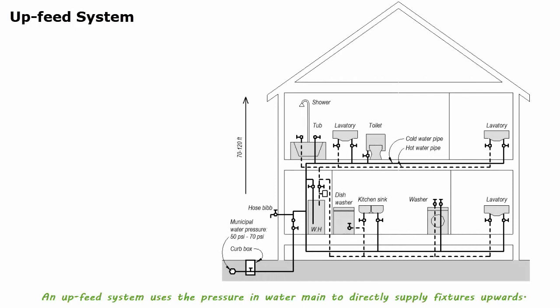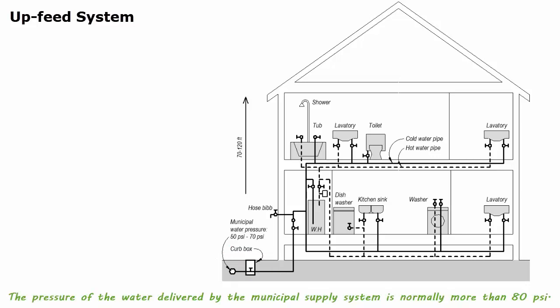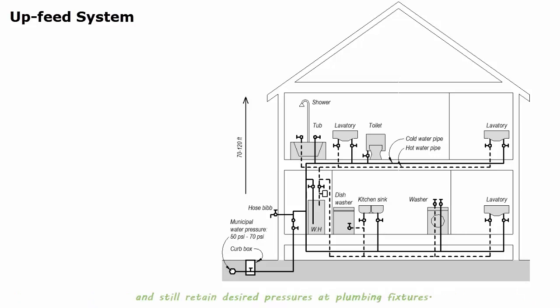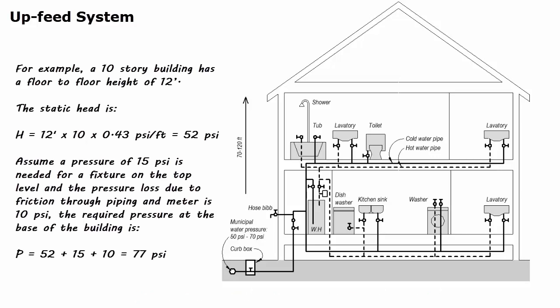An upfeed system uses the pressure in the water main to directly supply fixtures upwards. The pressure of the water delivered by the municipal supply system is normally more than 80 psi, which is large enough to raise water up to 8 to 10 stories and still retain desirable pressures at plumbing fixtures. For example, a 10-story building has a floor-to-floor height of 12 feet, and the static water head is 12 feet times 10 stories times 0.43 psi per foot.